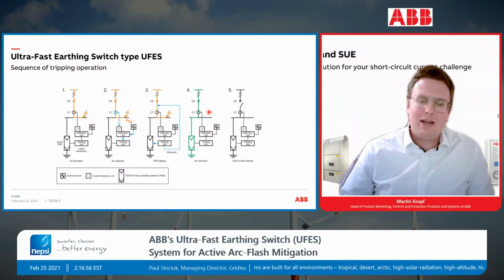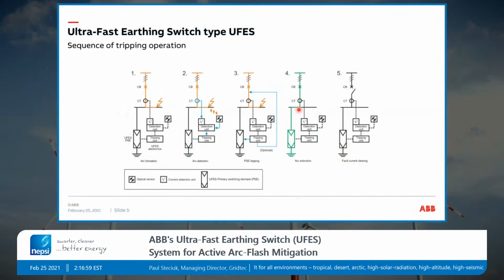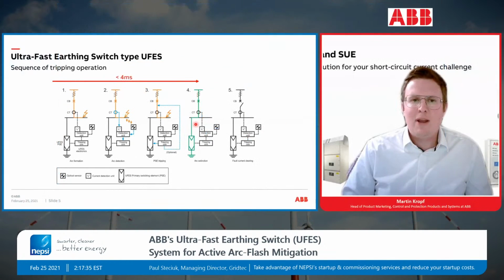Step number 4 is the essential one. We are actually then closing the earthing switch, and when this is happening, we are shutting off the arc. And how are we doing this? We are giving the current to ground a more attractive way. And this is via a 3-phase solid earth connection via the primary switching element. And the key topic is the timing. We are in step number 4 in less than 4 milliseconds. And then it's actually not that important anymore how long it takes between step number 4 and step number 5, because the current is not creating any damage anymore after step number 4. And this is actually how we are working.